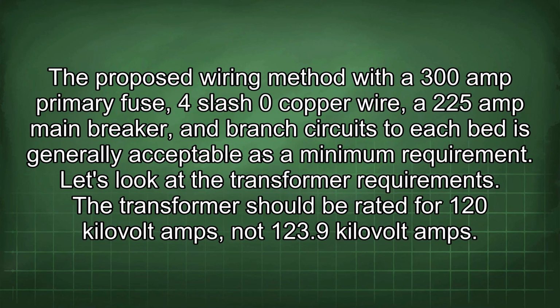Proposed wiring method with a 300 amp primary fuse, 4/0 copper wire, a 225 amp main breaker, and branch circuits to each bed is generally acceptable as a minimum requirement. Let's look at the transformer requirements.